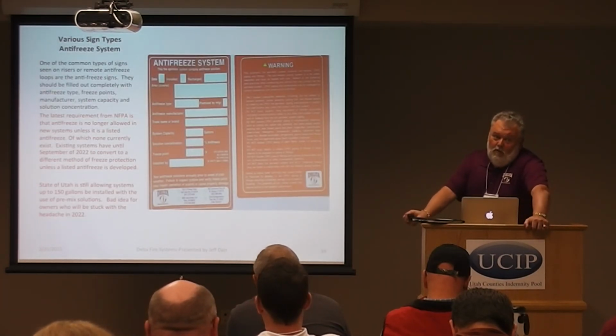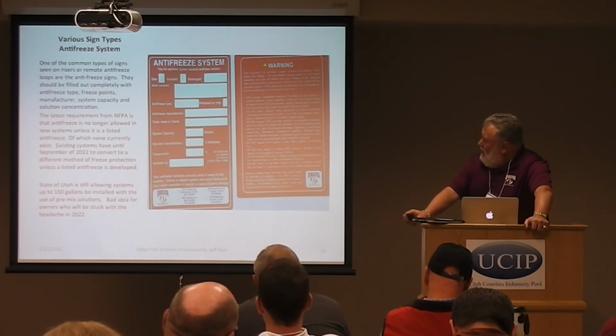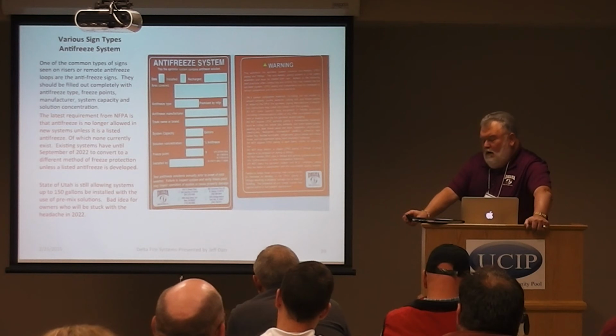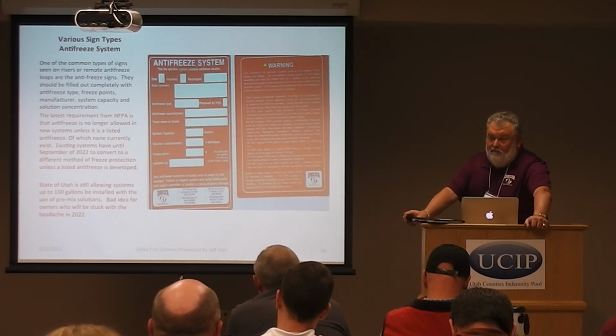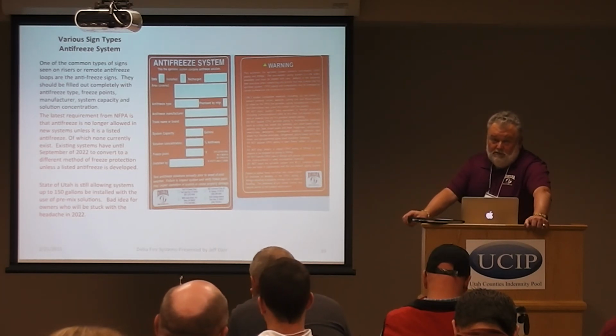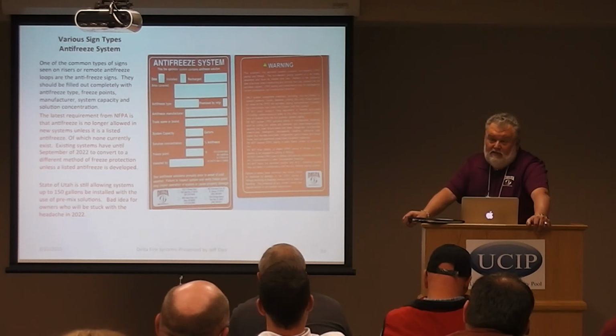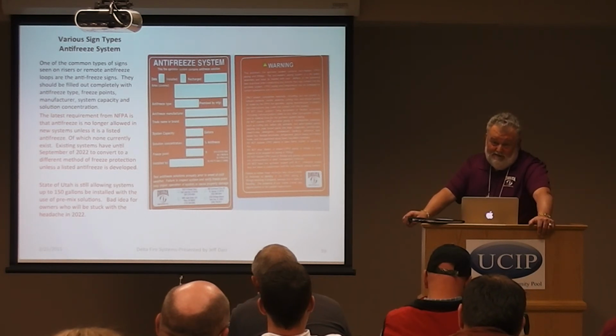Now, systems are also required to have various types of signs on them. Here's an example of an antifreeze system. Antifreeze was quite common in buildings in this area up until recently. NFPA, actually, there was a death in Truckee, California, because antifreeze is a combustible liquid in a fire suppression system. Sounds strange, but for years they were done just on small loading docks, grocery stores, and receiving areas. In the last 10, 15 years, residential systems and apartment complexes are now required to be sprinklered, but were never sprinklered in the past. And they put in antifreeze. We've seen 1,500 gallon antifreeze systems.